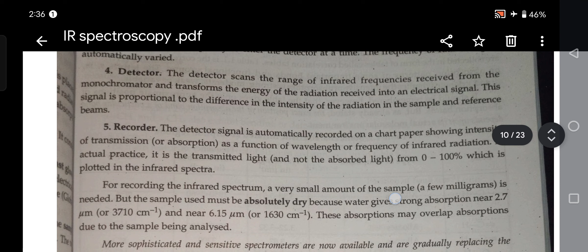The detector scans the range of infrared frequency received from the monochromator and transfers the energy of the radiation received into an electrical signal. This signal is proportional to the difference in the intensity of radiation in the sample and the reference beams. The recorder records the detector signal automatically on chart paper, showing intensity of transmission as a function of wavelength or frequency of infrared radiation.